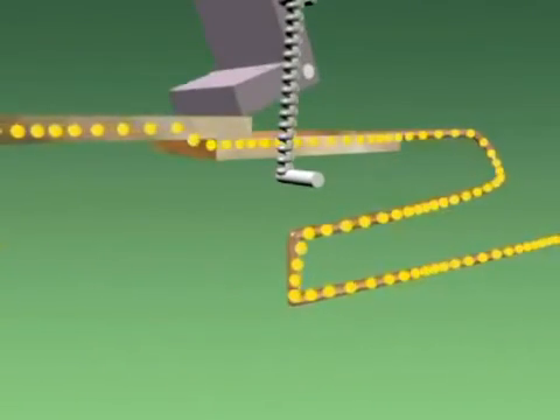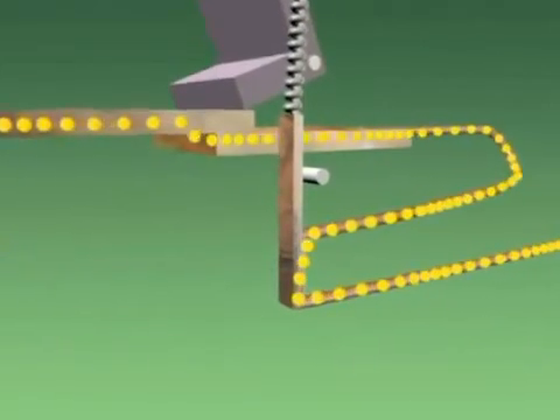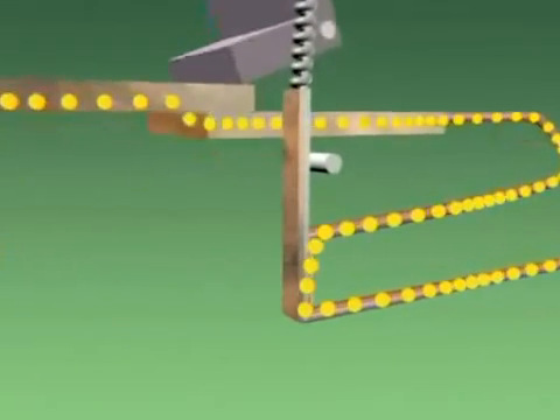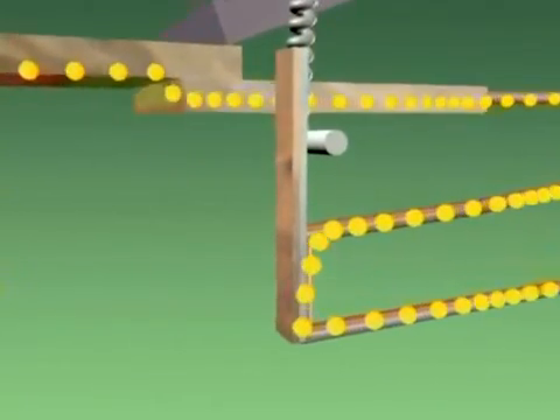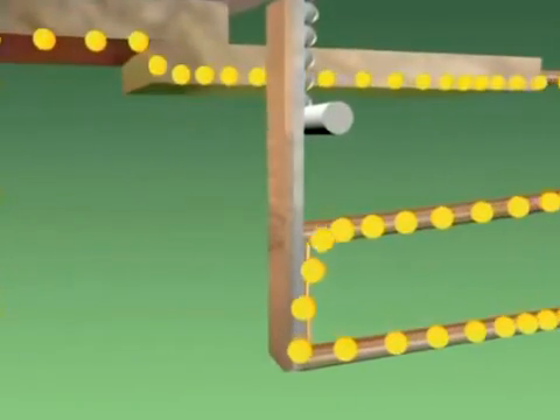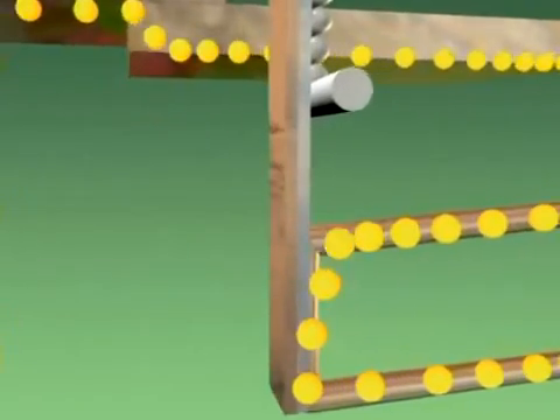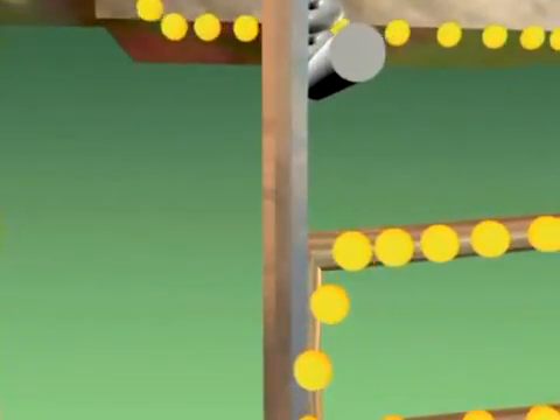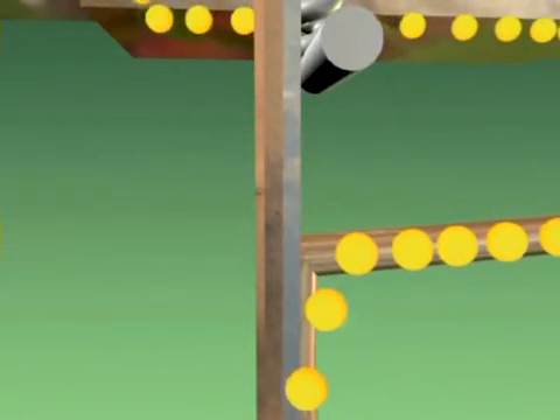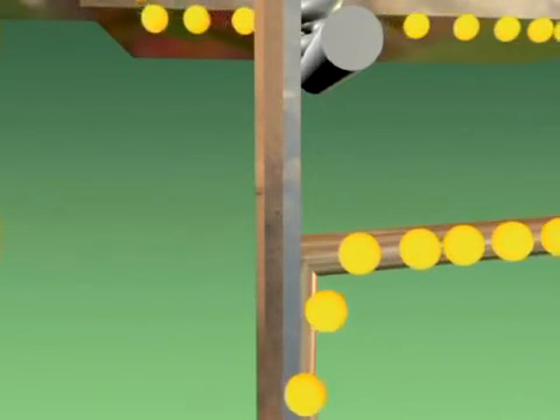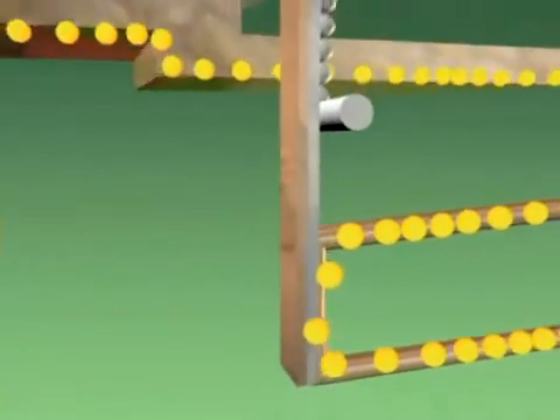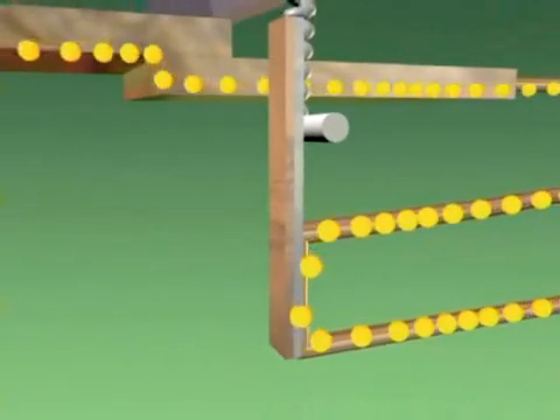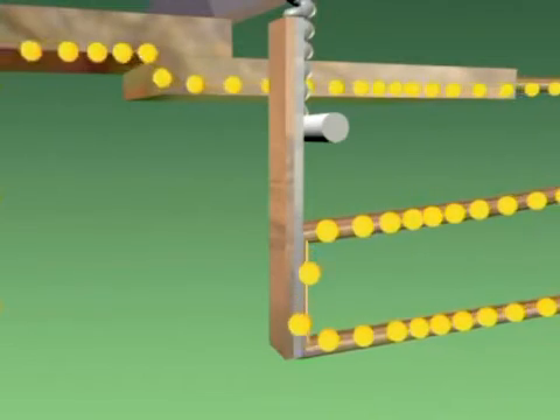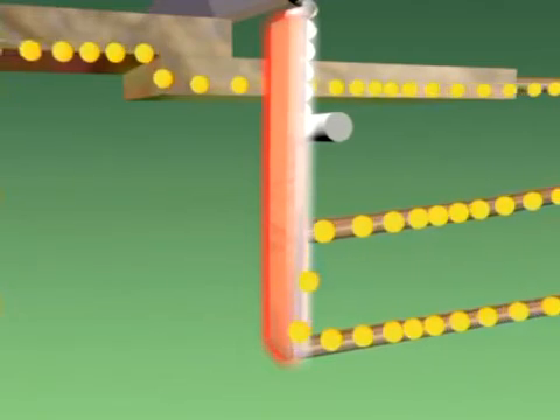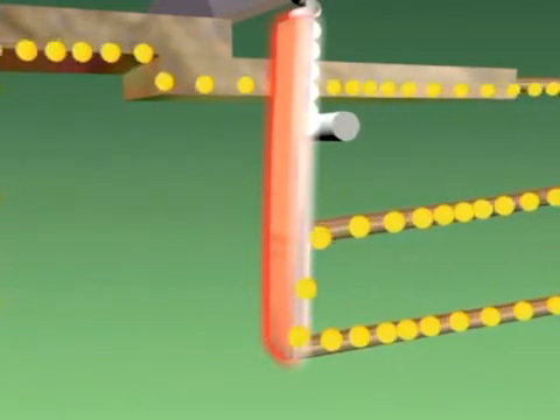A common device is a bimetal strip, which is included in the circuit so that current flows through it and heats it. All metals expand when heated, but different materials expand at different rates. A bimetal strip is composed of two metals. As current flow increases in the circuit protected by the breaker, the bimetal strip heats up, but one side expands faster than the other. That causes the bimetal strip to bend.